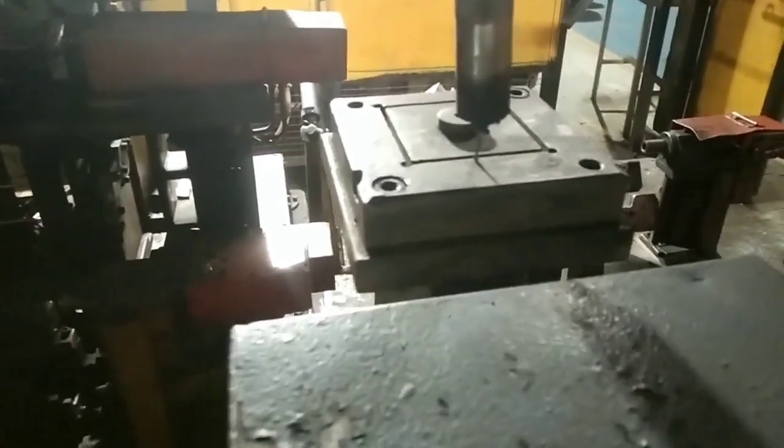How does this alarm occur? You can see that the hold lamp is on, which shows a red mark in the teach pendant. I am at dead TCP here — the auto TCP fixture shows that its wire got stuck at the metal piece because the surrounding fence area is already having a 24-volt supply. The wire gets touched with it, receives 24 volts, and so it shows wire sticking or short.